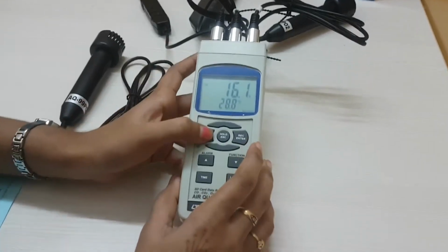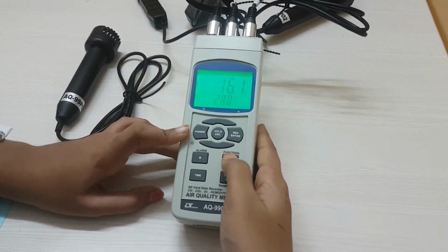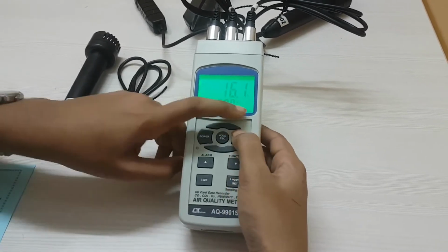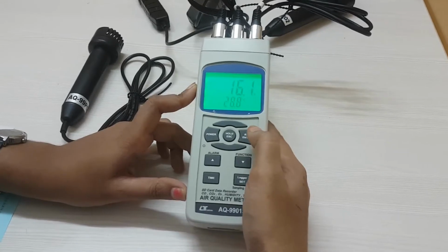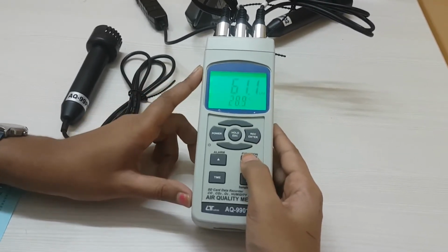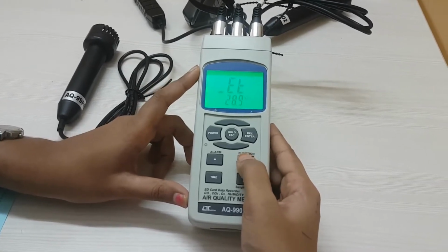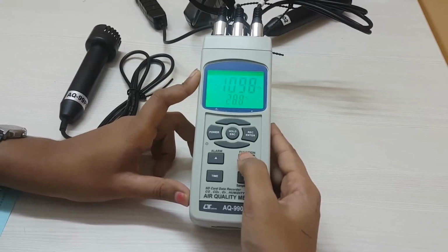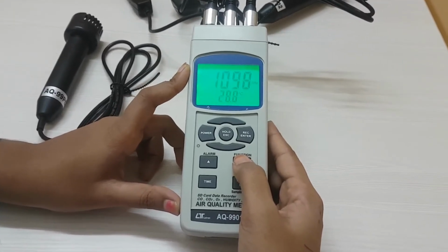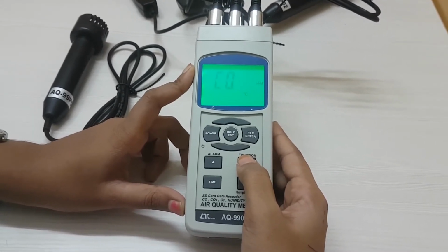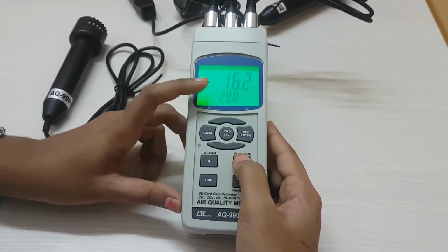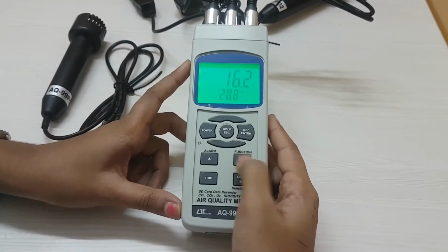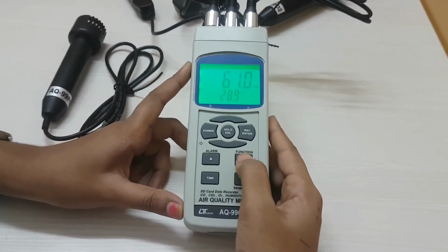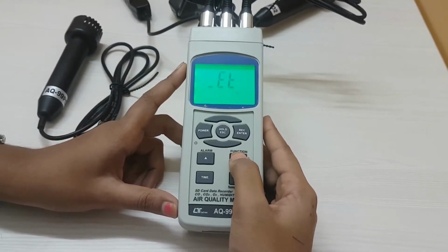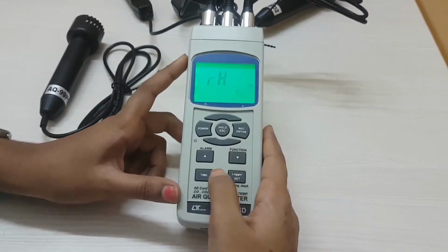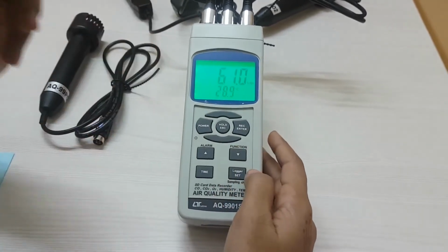Now coming to the measuring, let's come to the function. Presently, it was recording. I just turned it off. It is showing RH, dP, wet bulb temperature, CO2 readings. Currently it is 1098, and CO, and oxygen readings it is showing as we connected the oxygen probe. Here we can monitor dew point temperature, wet bulb temperature, CO2, CO, etc. We can also change the readings from degree centigrade to Fahrenheit and Fahrenheit to degree centigrade.